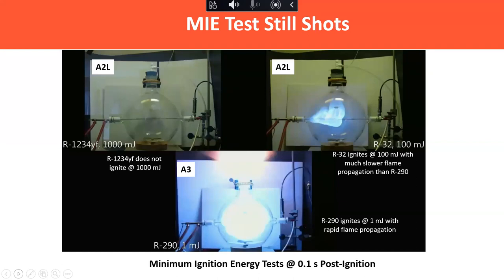Just compare that to the one above on the upper right, R32. Notice at 1 millijoule, nothing happens. So they keep cranking up the energy, and finally you get to 100 millijoules, 100 times the energy, and then you get an ignition of the R32. Again, you see it's not nearly as extreme.